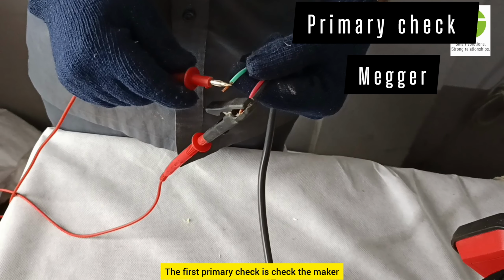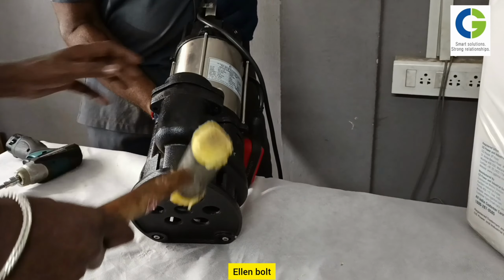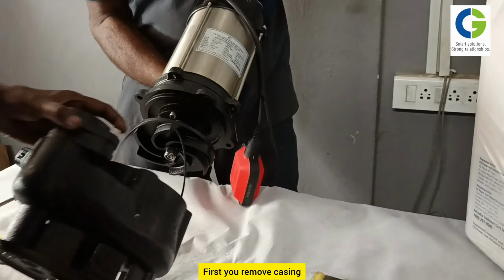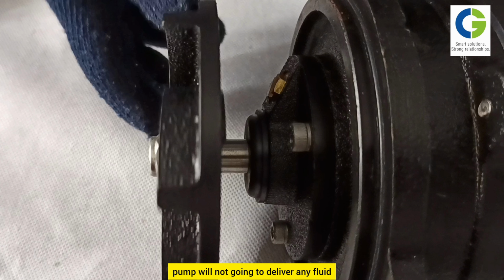Check the power supply to ensure the pump is receiving the correct voltage: 220 volts for single phase and 415 volts for three phase. The first primary check is to check with the megger whether the winding is in good condition or not. Remove the nylon rope and keep the pump in a safe place to open it. By using the Allen key set, you can remove all these Allen bolts. First, remove the casing and check for any blockages in the casing or in the impeller. Due to a blockage in the impeller or casing, the pump will not deliver any fluid.